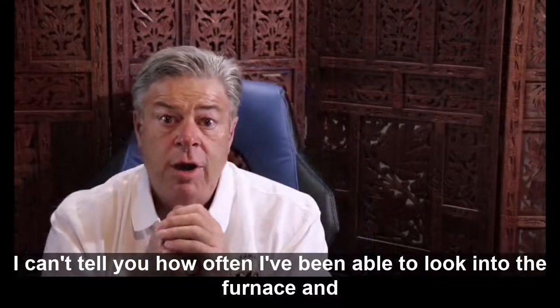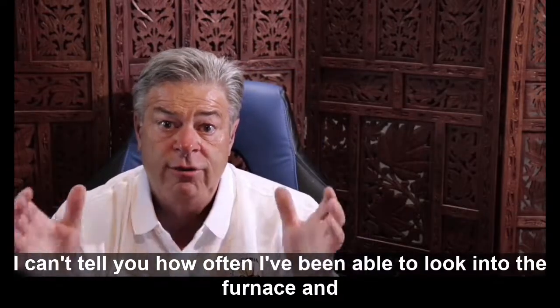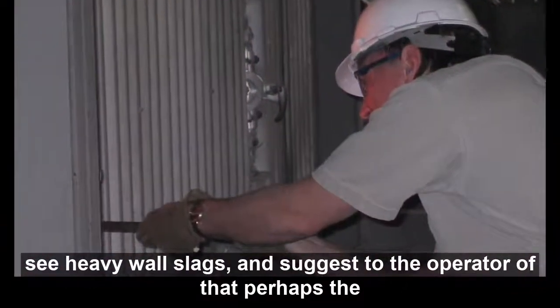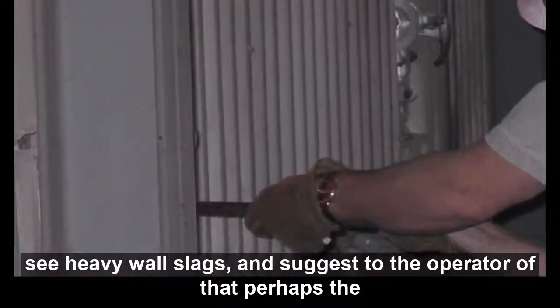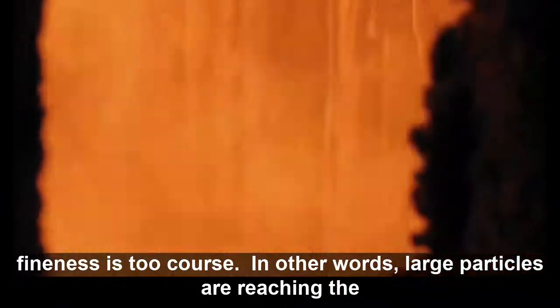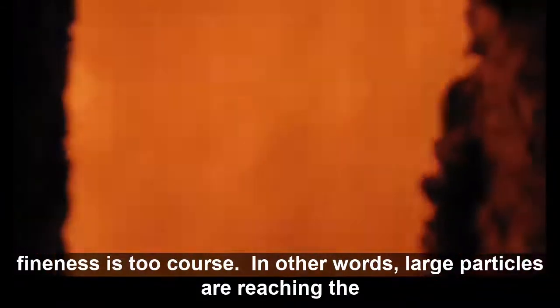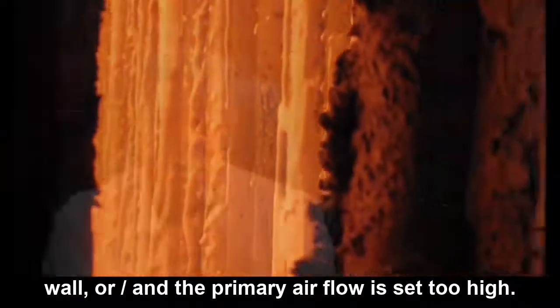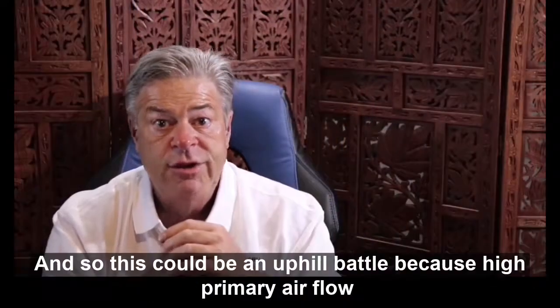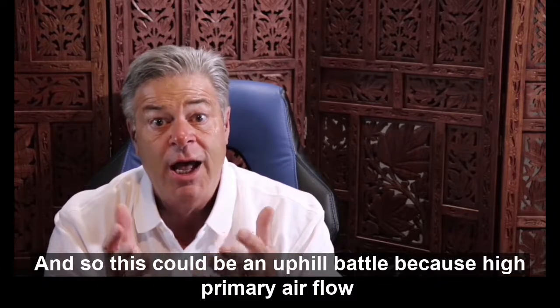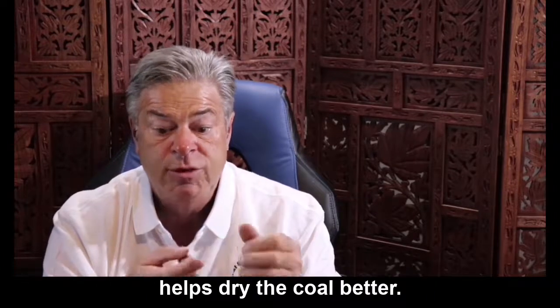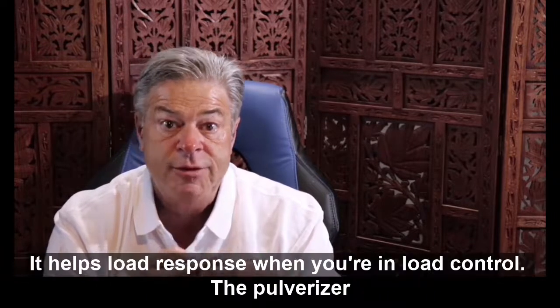I can't tell you how often I've been able to look into the furnace and see heavy wall slags and suggest to the operator that perhaps the fineness is too coarse, in other words, large particles are reaching the wall, and the primary airflow is set too high. This could be an uphill battle because high primary airflow helps dry the coal better. It helps load response.